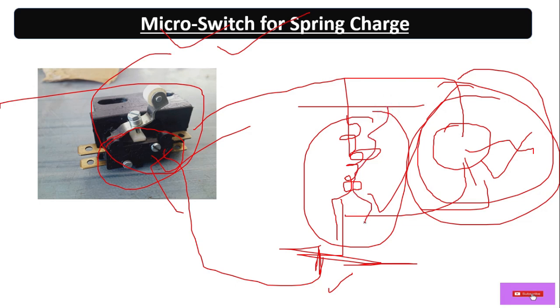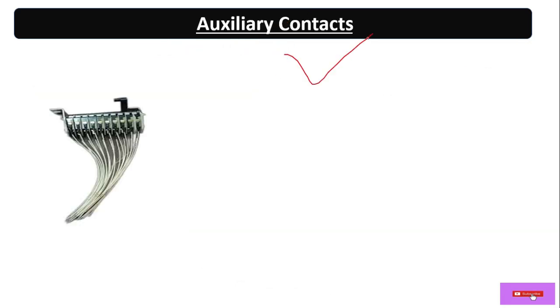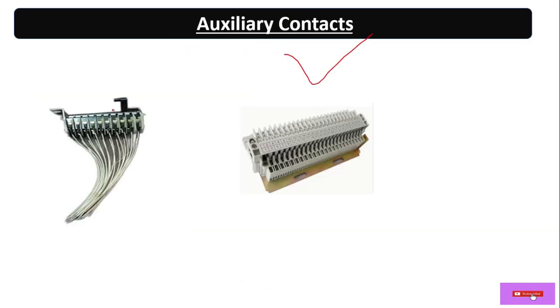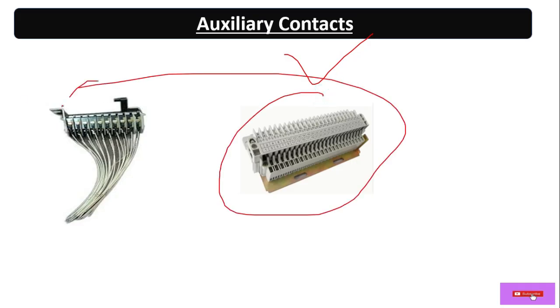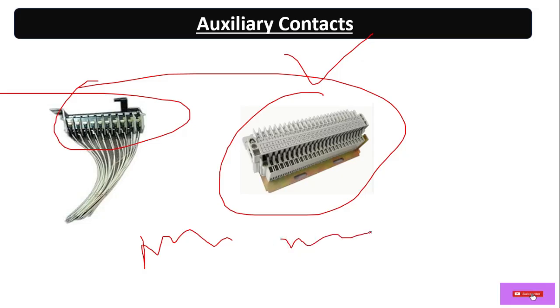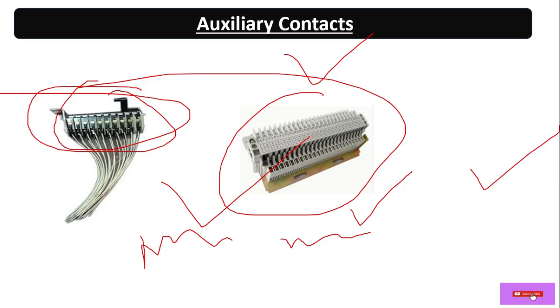The ACB also has external auxiliary contacts — normally open and normally closed — for on condition, off condition, and trip condition. Through the auxiliary contacts terminal box we can take the status signals.